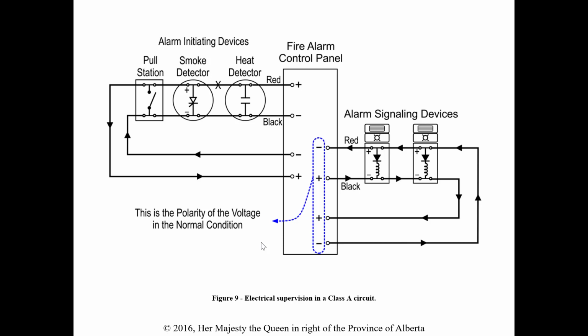So the other one we talk about is the Class A circuit, and it's very similar. They're run in parallel just like in Class B. The big thing, and I'm sure you can see right away, is there is no end-of-line resistor. The loop actually goes all the way back to the panel. There's an advantage to this, and obviously disadvantages as well in regards to the wiring methods, because you have to come all the way back to the panel. But the advantage is if we have a break at this point, at point X, these devices will continue to work because they're backfed from the panel this way. So with this loop back, if there's a break, we could still have every device working even though we've lost a connection point.